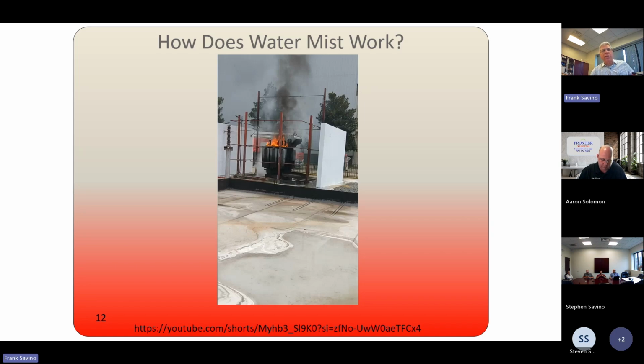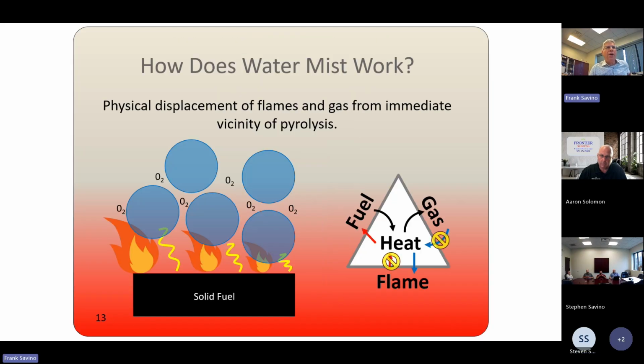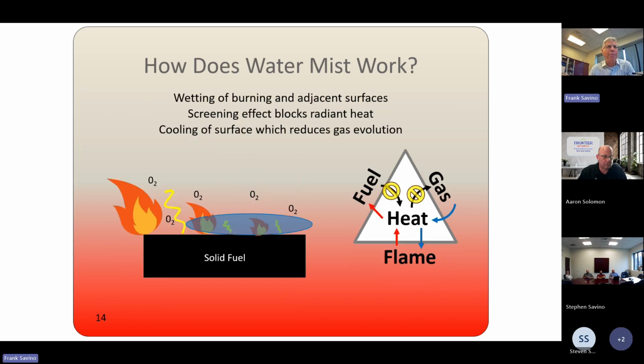So to answer your question, yes, that extinguished that fire. Got it. Okay, so other ways that water mist system works, I call it the birthday candle effect. It's the physical displacement of flames or gas away from where the pyrolysis is happening. So when you discharge the water mist toward the fire, it's actually moving the heat and the flames away from the fire, taking away that heat source. That's another principle of operation.